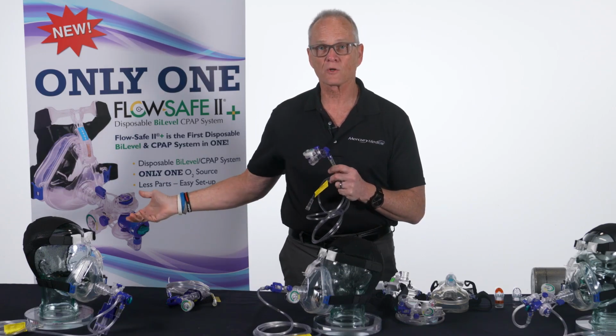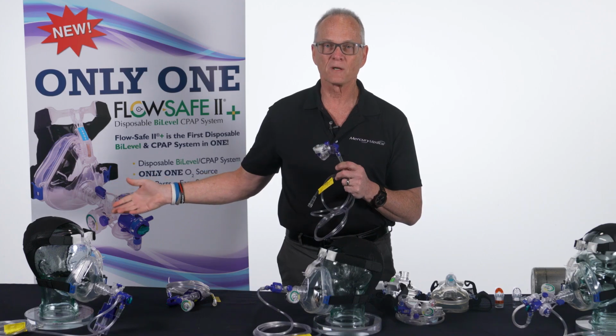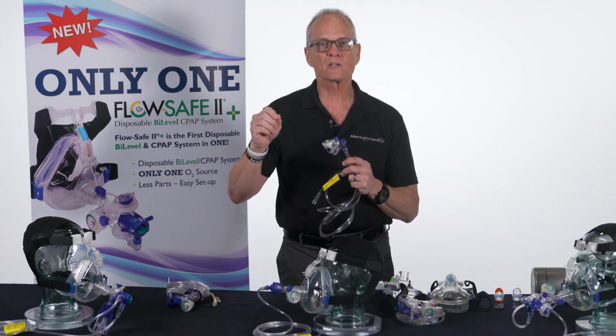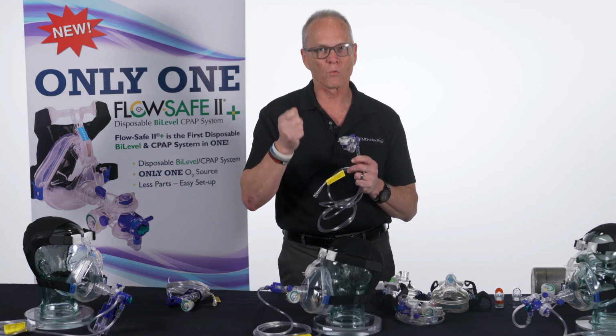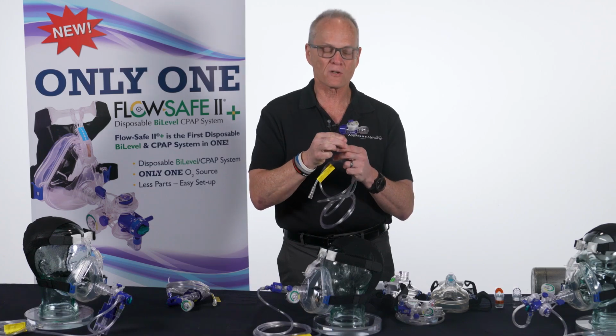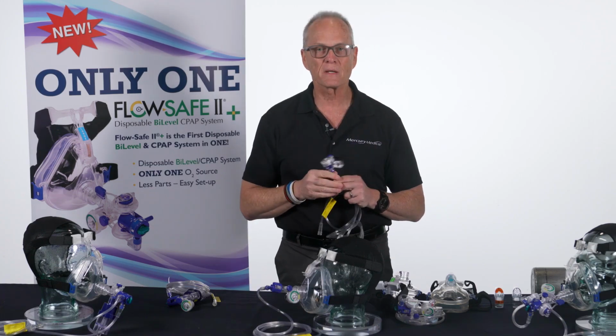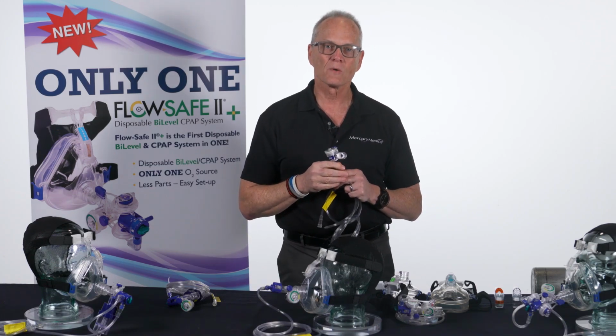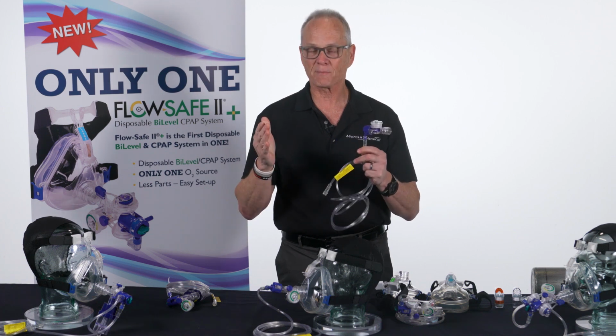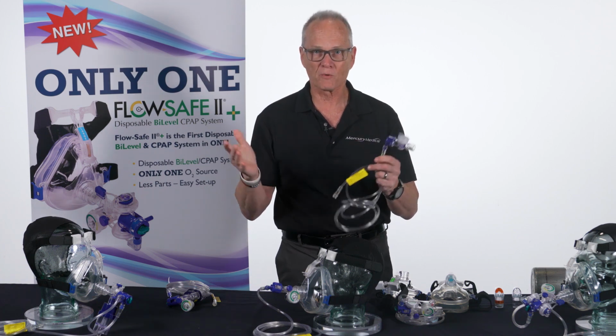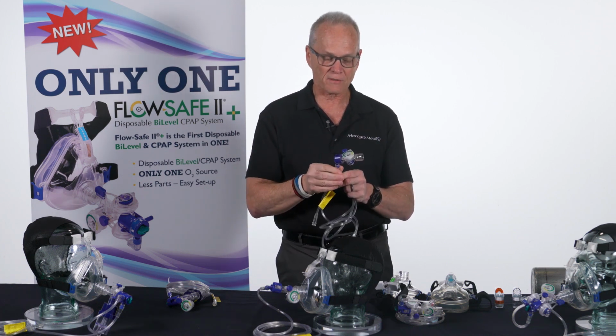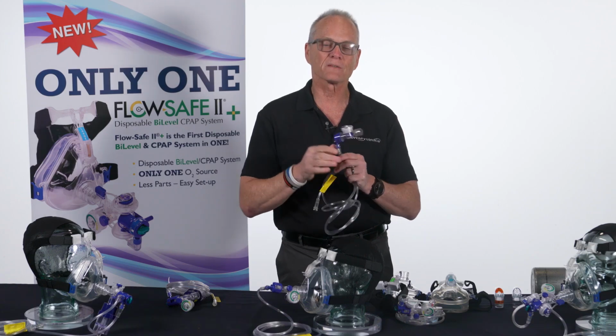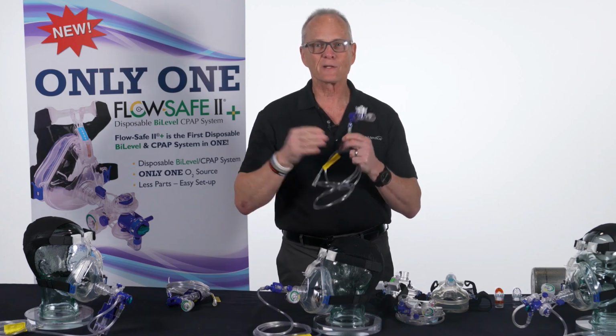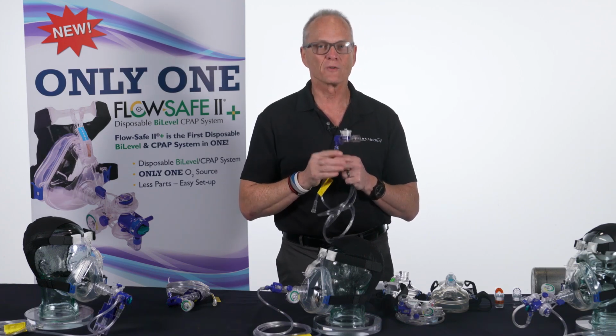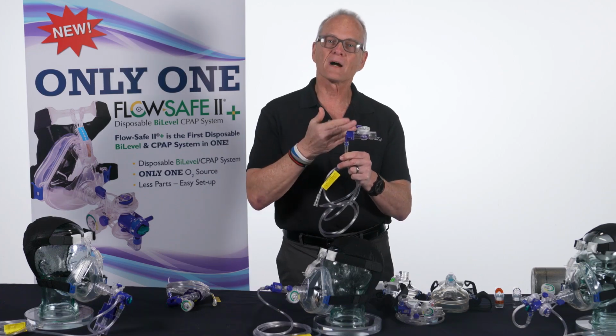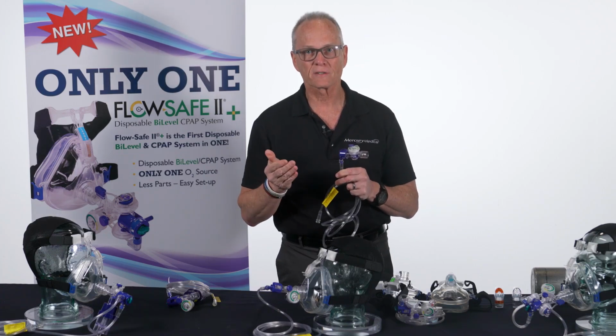I didn't go back and turn up the hose bib to get more water, but I changed the forward velocity of the water. It's the same thing here. So this is going to speed up and meet the patient's demand. So it's important that any CPAP device is able to do that. So that's how that actually works. Because I've had people say, well, geez, 8 liters a minute won't get it. And they're right, it won't. But in a device like FlowSafe, it does.